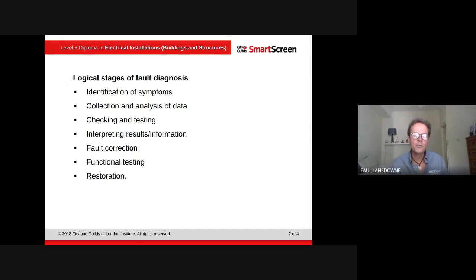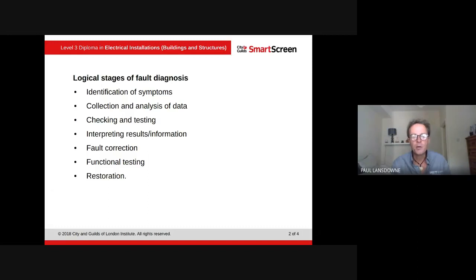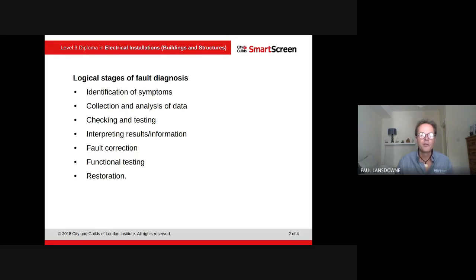By looking at those different types of results we could determine what type of problem it was. For example, if we had a continuity test on a neutral going to a socket or a cooker and the neutral wasn't arriving at that socket, we would realize there might be a break in that circuit and could follow it through to see if it had been damaged anywhere along the line.